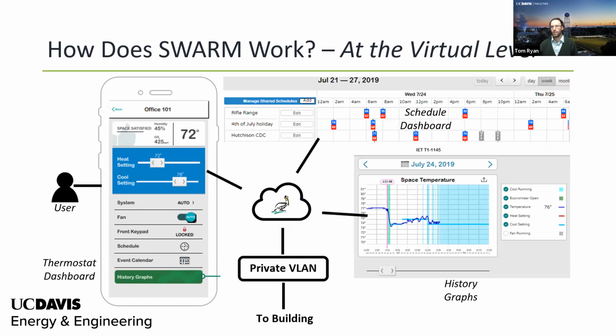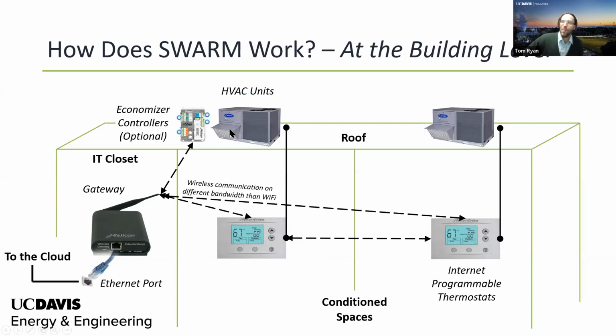I should also say on that last slide, I didn't really mention it, but the economizer controls are, sorry about that. So there are thermostats, standard temperature thermostats, which is their basic. They also have ones that are able to sense CO2 and humidity. We don't use a lot of the humidity control, but we could. And you can see in here, it has a standardized control for the economizer as well. And that's one of the things that actually makes the economizer effective, that it's standardized and it's simple and it's one system. A lot of the problem is Carrier has a certain control schematic and way of controlling the economizers, and then Honeywell has one, and all of these different companies have different ways of controlling, which makes it a little bit more complicated for a technician to figure out as well. Next slide.